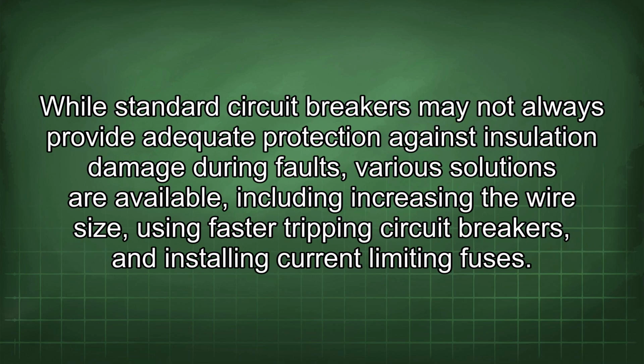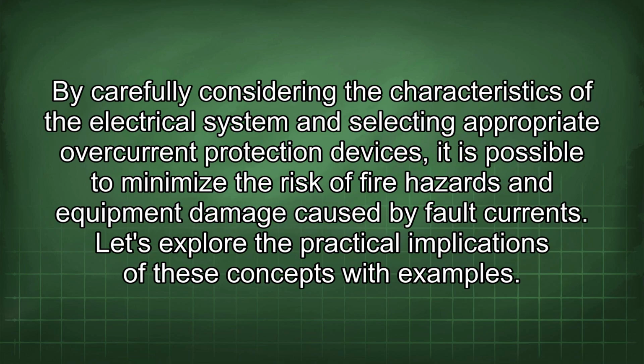While standard circuit breakers may not always provide adequate protection against insulation damage during faults, various solutions are available, including increasing the wire size, using faster tripping circuit breakers, and installing current-limiting fuses. By carefully considering the characteristics of the electrical system and selecting appropriate overcurrent protection devices, it is possible to minimize the risk of fire hazards and equipment damage caused by fault currents. Let's explore the practical implications of these concepts with examples.